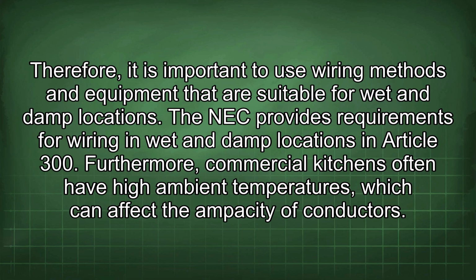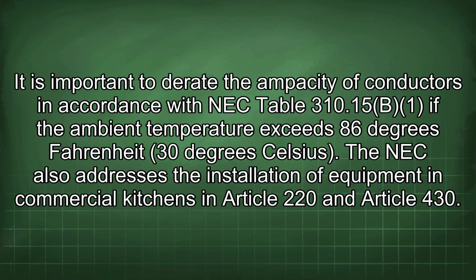Furthermore, commercial kitchens often have high ambient temperatures, which can affect the ampacity of conductors. It is important to derate the ampacity of conductors in accordance with NEC Table 310.15 if the ambient temperature exceeds 86 degrees Fahrenheit, or 30 degrees Celsius.